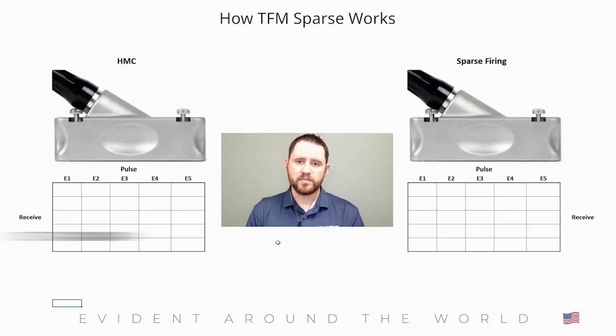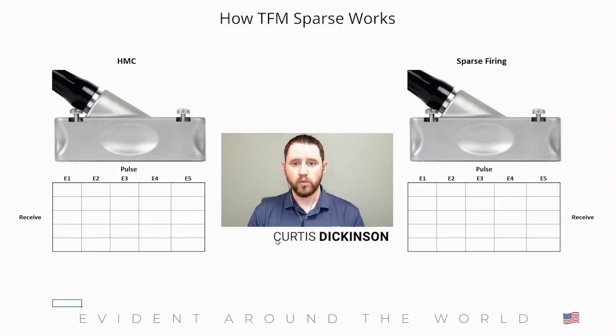Let's begin with a brief explanation on how the sparse firing mode works on the OmniScan X3. In a typical TFM inspection, we utilize FMC, or full matrix capture, as the means of pulsing and receiving signals from a phased array transducer. And one of the questions that we often get with the sparse mode is, is this a form of HMC, or half matrix capture? And the answer to that is no.